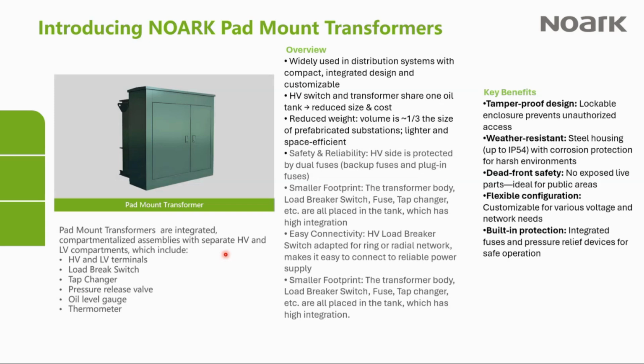The other type of transformer we actually want to talk about in this training is the pad mount transformer, and it's really our main focus. We do have pad mount transformers rated up to 35 kV, and in terms of capacity, up to 10 MVA. But in terms of the UL certification that we have, it goes up to 5 MVA.